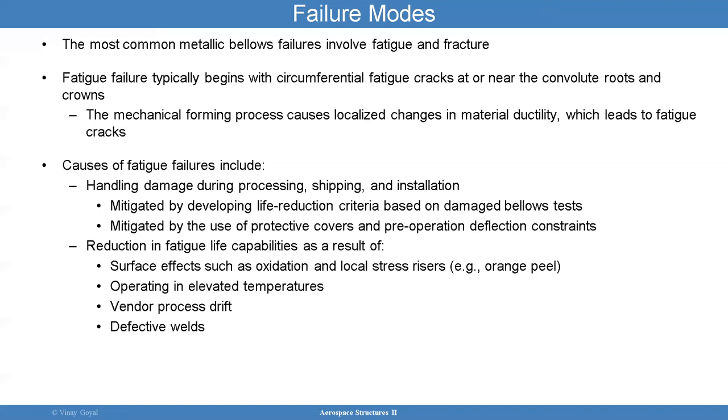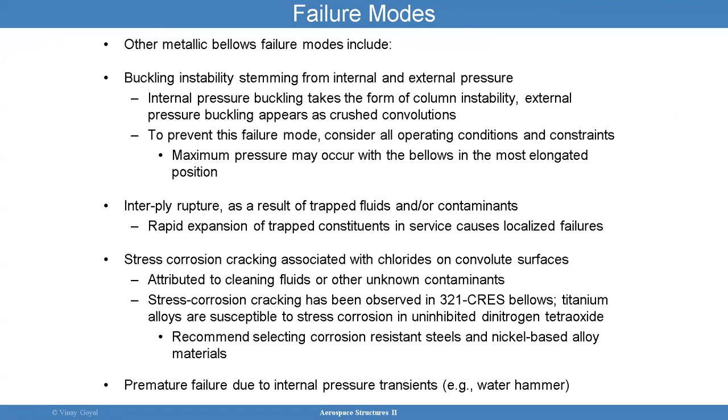Failure modes are complicated. The most common metallic bellows failure is fatigue and fracture. Fatigue is usually circumferential fatigue cracks near the convolution roots and crowns. The mechanical forming process causes localized changes in material ductility, which leads to fatigue cracks. Causes of fatigue failure include handling and installation, cyclic pressure events, environmental effects like surface oxidation at elevated temperatures, vendor process drift, and changes in how the bellows are made over time. Welds can be defective.